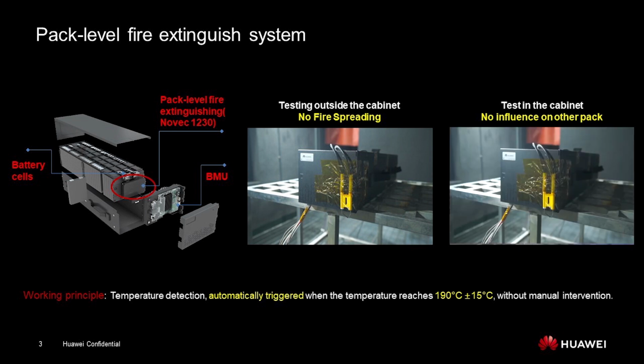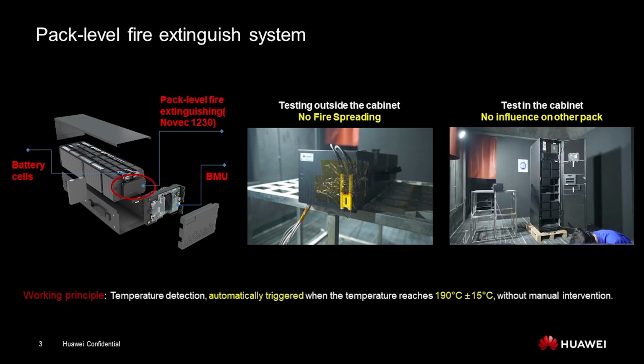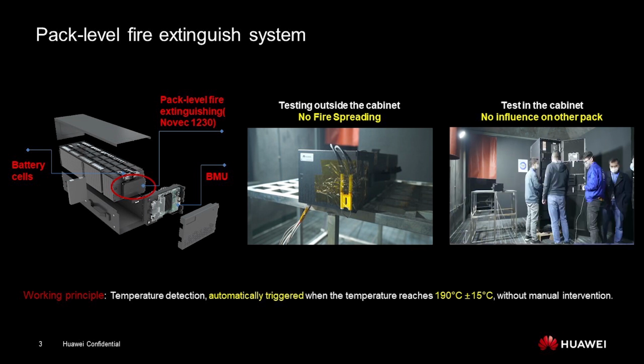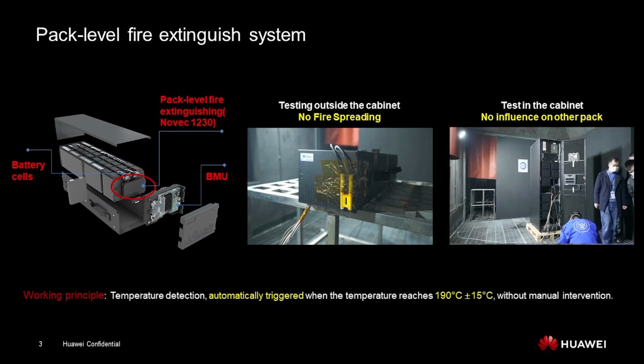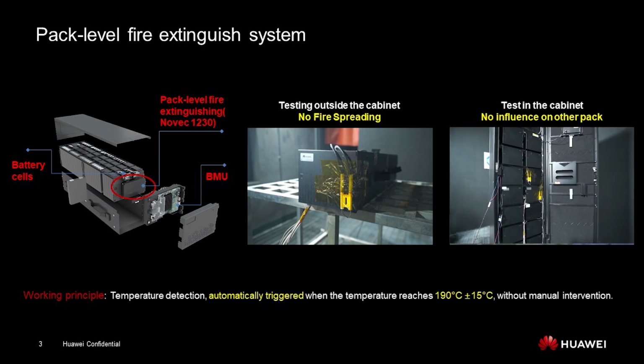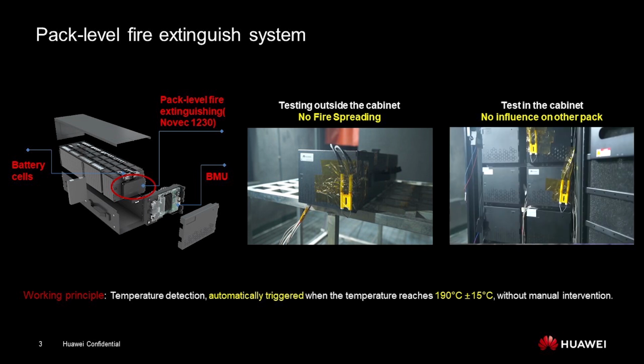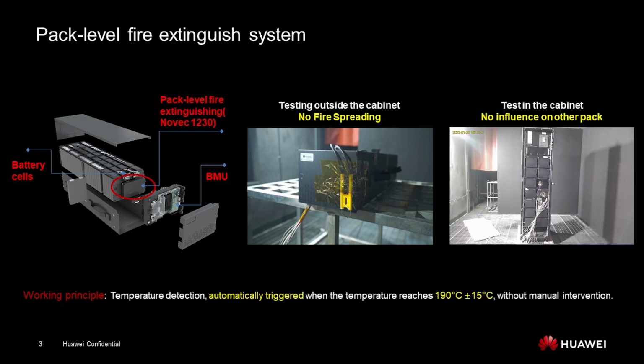So we have done this test in a third-party organization, manually raising the temperature to thermal runaway and manually igniting. The result shows it can be triggered in around 15 seconds. The fire can be cut off. So we have these 2 ways: the internal short circuit prediction to solve the gradient type and the pack level fire extinguishing system to solve the burst type.